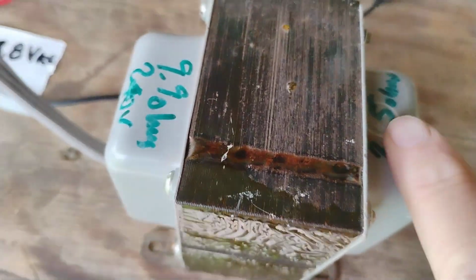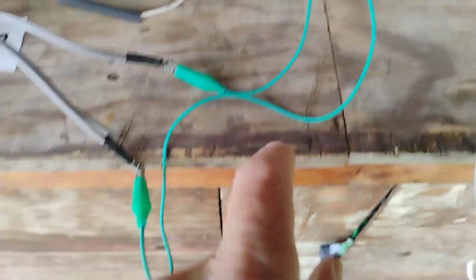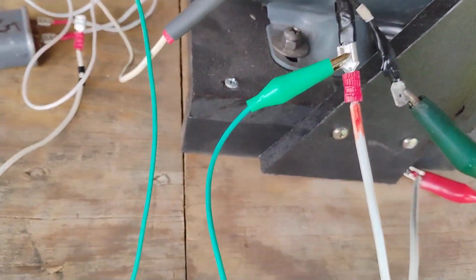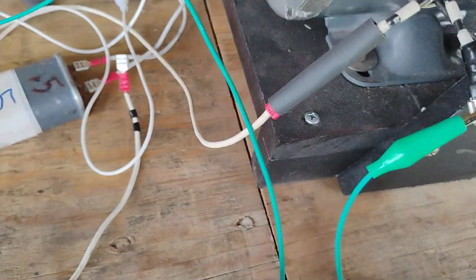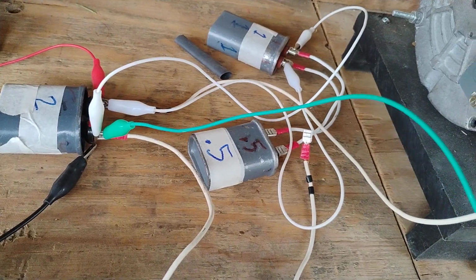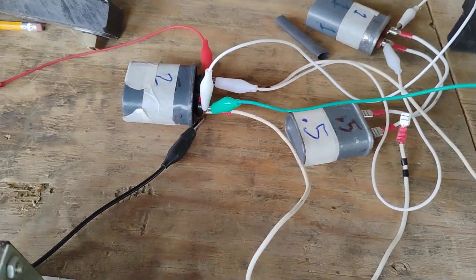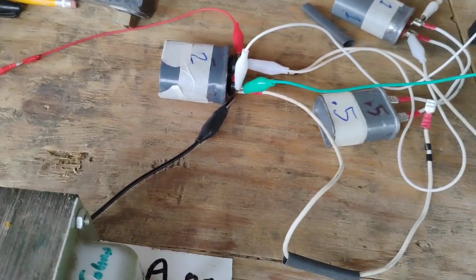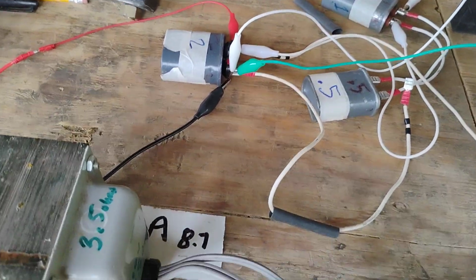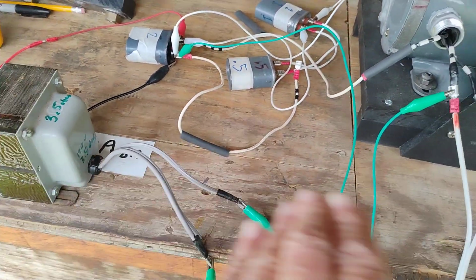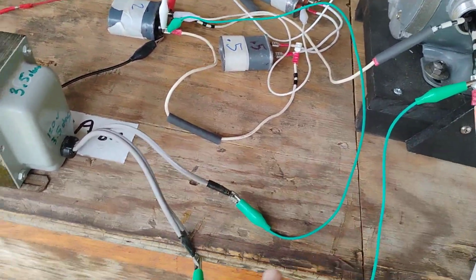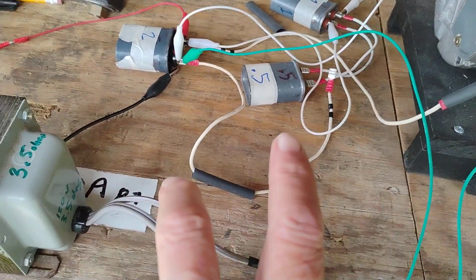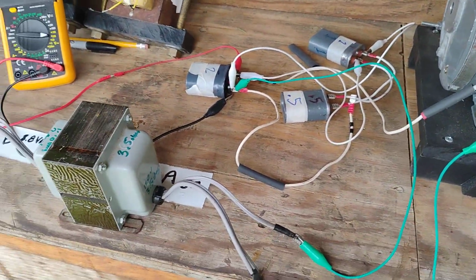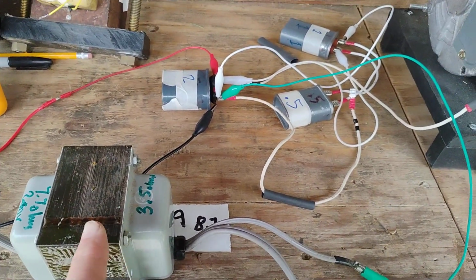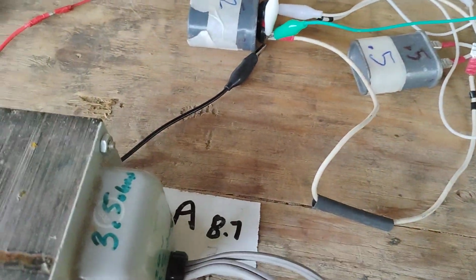Okay, the 3.5 ohm side is now in series. You can follow the green wires. Here's the L2 line, it goes into it, comes out of it. I think this is called a transformer inverter, V-E-C-T-O-R configuration, because it is in series with an AC line. The AC is going like this, and it's in series - not like this way and this way in parallel like you normally hook up a transformer. You have this transformer in series on the L2 line.